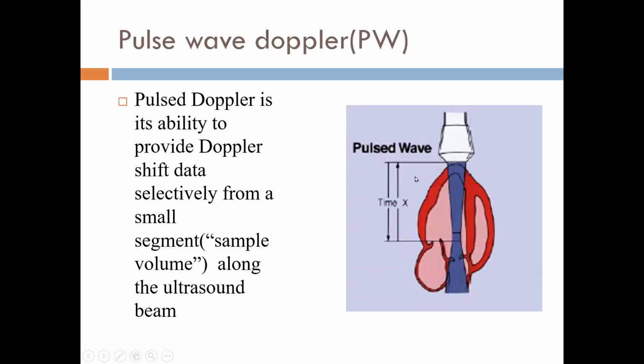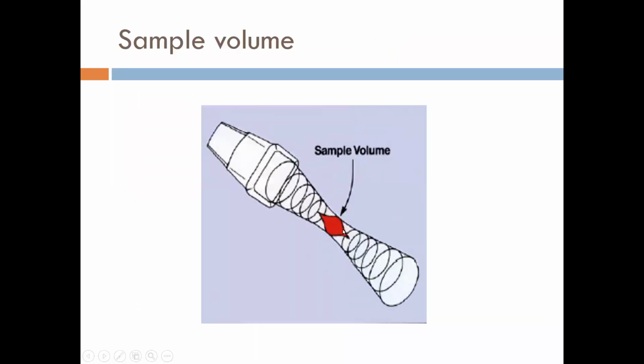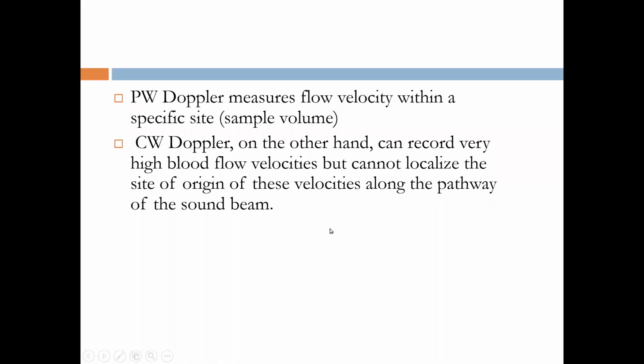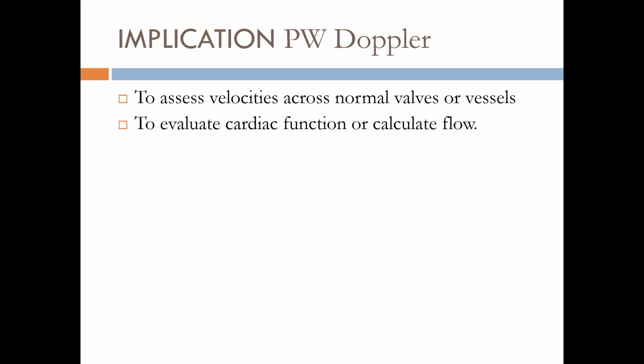In case of pulse Doppler, only a selected area is notified, what we call a sample size, and in that particular area only the velocity is measured. So this blue color jet is called the sound beam, or what we see as a cursor on our 2D screen. If we select a particular area on this cursor and press pulse Doppler, you will be able to measure the velocity only at that particular point. But if you press continuous wave Doppler, you will measure the velocity across the whole length of the cursor. So in pulse Doppler, the sample volume will be very small, but in continuous wave Doppler, the sample volume will be across the whole length of the sound beam.